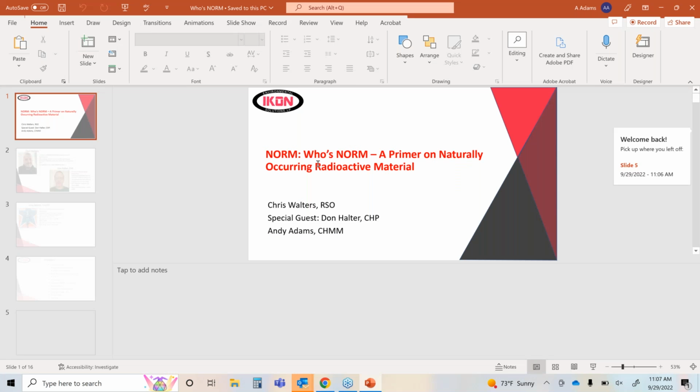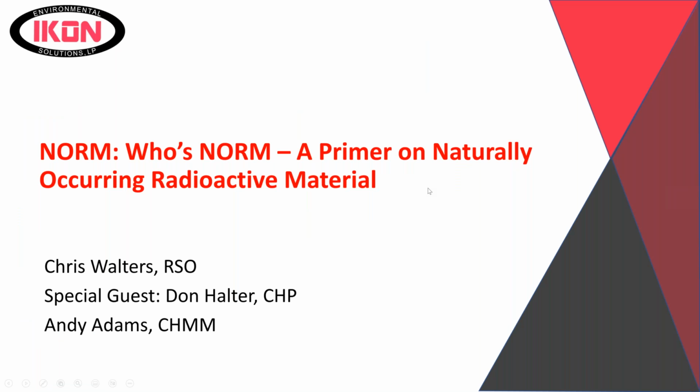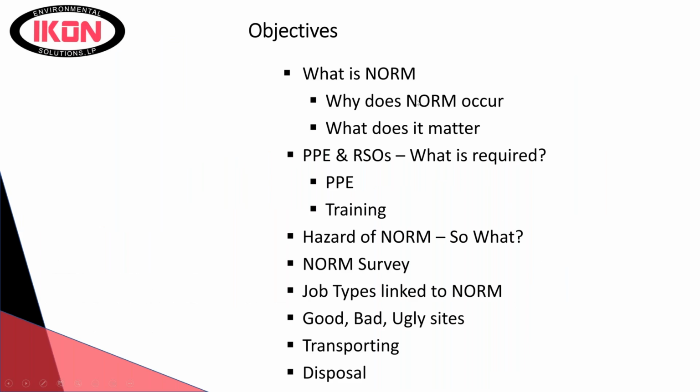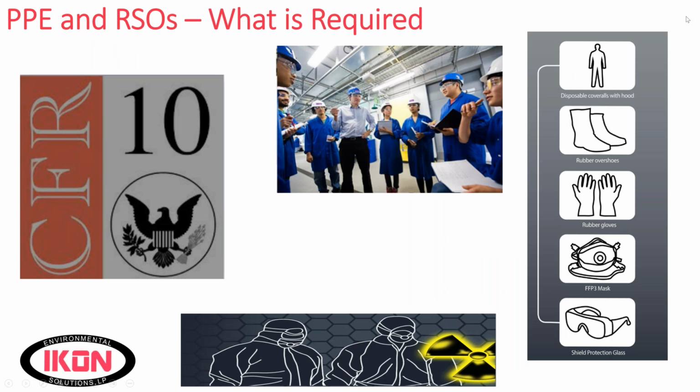Chemistry is a lot of... people don't understand that there's not one radiation detector that's fantastic for every type of radiation. When you have naturally occurring radioactive material, you're going to have alpha particles, beta particles, gamma rays, even sometimes neutrons if you're out in the uranium mine somewhere. And these require different types of detectors. So you've got to make sure that you have the proper detector for what it is you're looking for. If you're looking for gamma rays coming out of some radium deposits, you're going to need something that's very good for detecting gamma radiation. If you're looking at lead-210 that's alpha and beta, you obviously need a detector that can detect the alpha and beta particles.